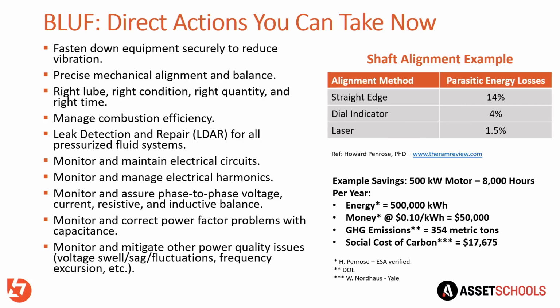On inductive balance, this is something that you really want to focus on when you're having your motors rebuilt, rewound. Inductive balance is the efficiency and effectiveness with which the electric motor converts electrical energy into mechanical energy, right? And you want that to be balanced across all phases. If you're inductively out of balance, that will produce a mechanical unbalance as well. And then, of course, power factor. You want to ensure that you are properly correcting power factor. So we typically need to add, I've actually never seen where we need to add resistance.